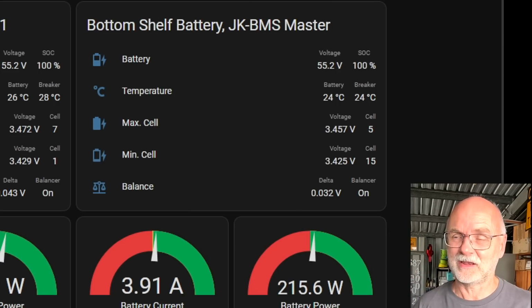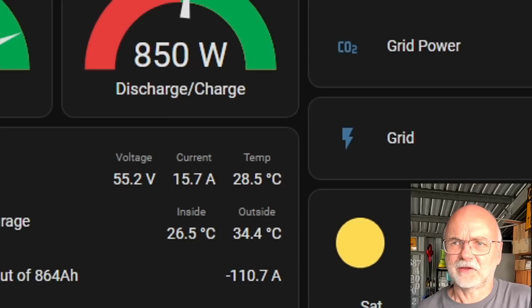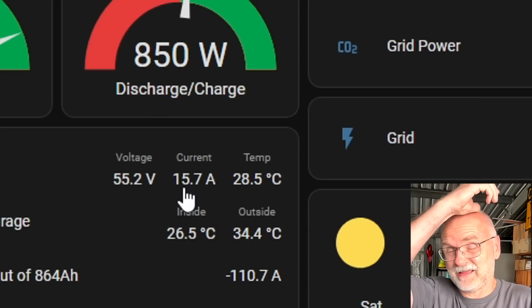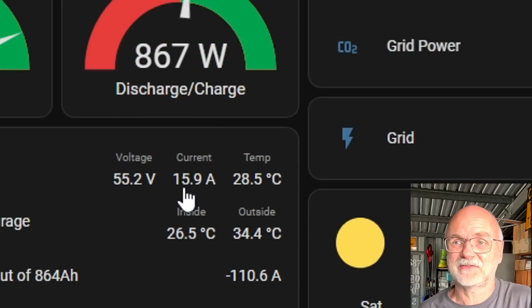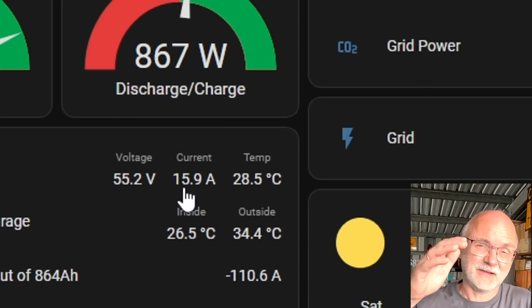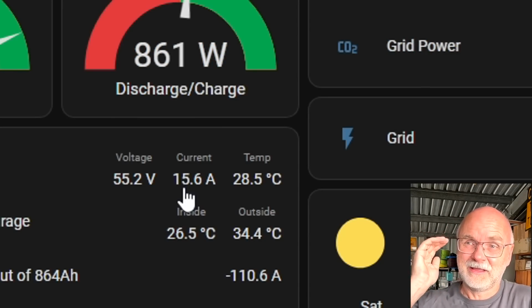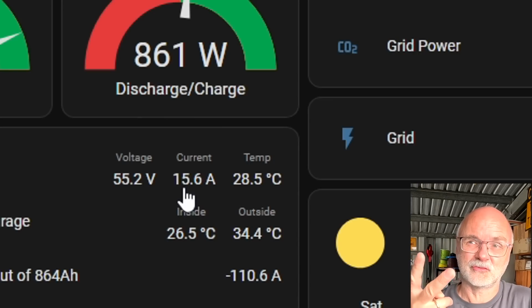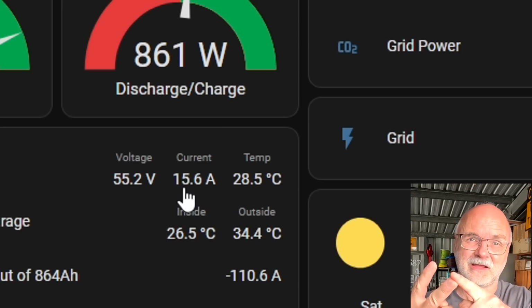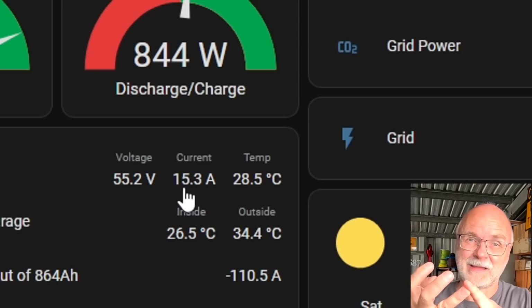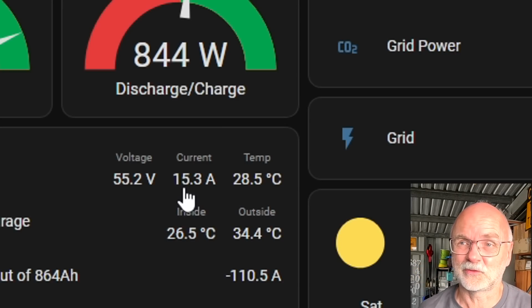That is incredible. So I think we're getting close now because the charging current into these three batteries has reduced to 15.7 amps, so we're far under these 17 amps now. The second trigger for the smart shunt to reset to 100% is now true — voltage and under this tail current. Now the 3-minute timer is running. Don't know when this was started.